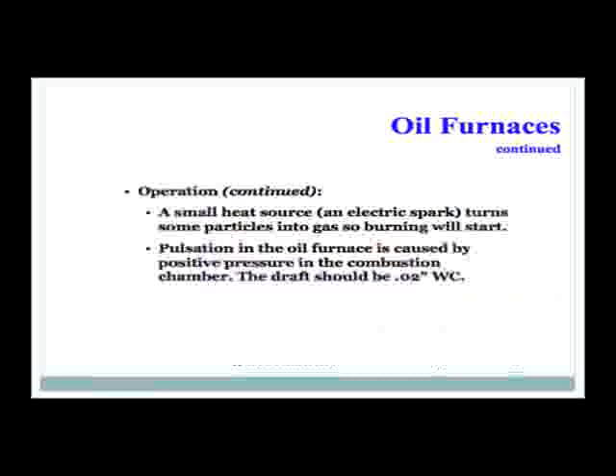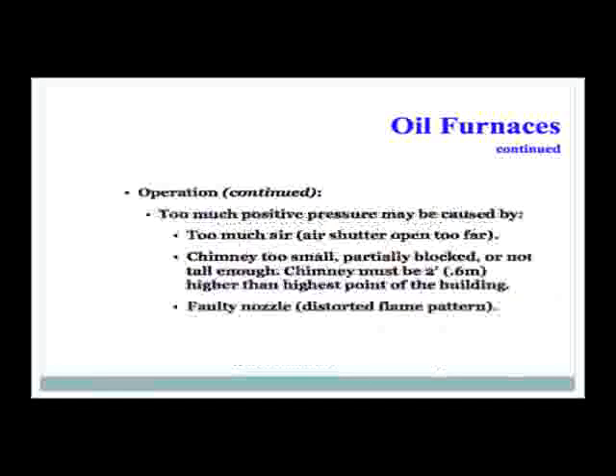Pulsation in the oil furnace is caused by a positive pressure in the combustion chamber. The draft should be 0.02 inches water column. Too much positive pressure may be caused by too much air, air shutter open too far, a chimney that is too small, partially blocked, or not tall enough. The chimney must be two feet higher than the highest point of the building. Pulsating and positive pressure can also be caused by a faulty nozzle.